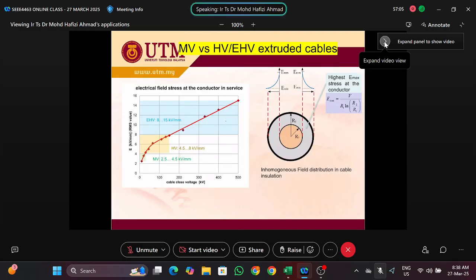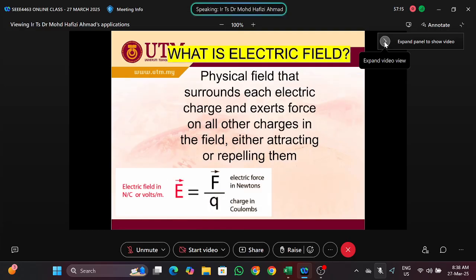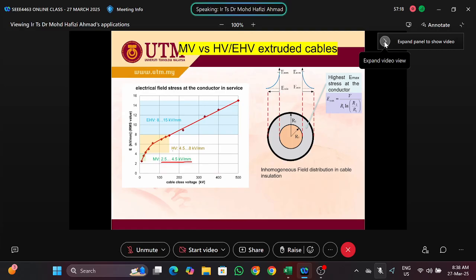Okay, so you might see that for the medium voltage cables, basically the electric field, this I took from, I can't remember, maybe from CIGRE or IEEE or IEC brochure or standards, right? So you might see that the medium voltage cables, their electric field is within 2.5 to 4.5 kV/mm. But for high voltage or extra high voltage cables, the electric field is higher compared to medium voltage. So that's why they cannot tolerate bigger voids inside the XLPE, inside the insulations.